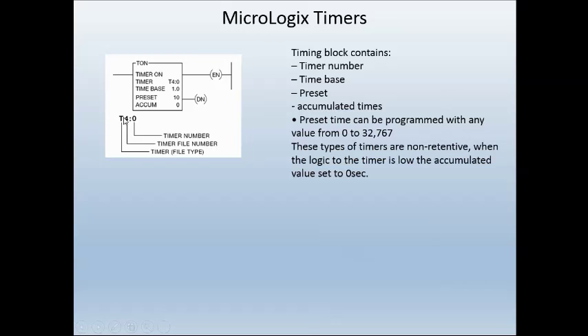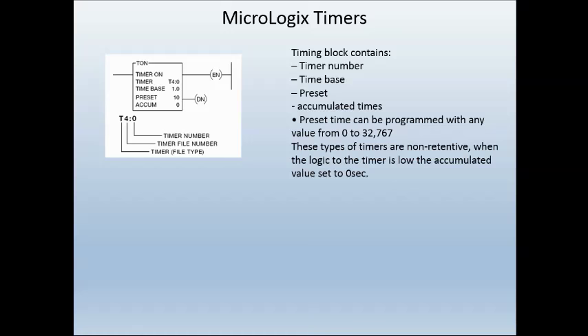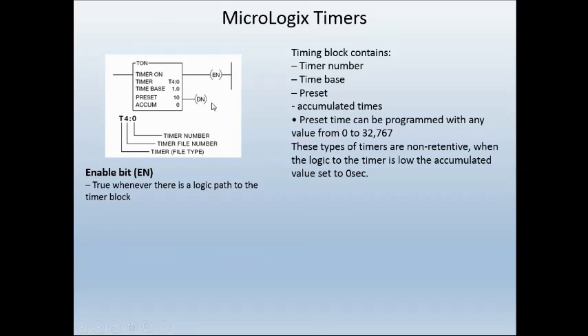The preset value can be programmed with any value from 0 to 32,767. The file structure for a MicroLogix — and the majority of controllers used with RSLogix 500 — is always going to be T for the file type. T is always for timers, and so is file number 4. Then you have the name of your timer. These timers are non-retentive: when the logic to the timer is false, its accumulated value will be set to 0. Your timer is an output, and as soon as the logic in front of it goes false, the accumulated value automatically resets to 0 — hence it is non-retentive.